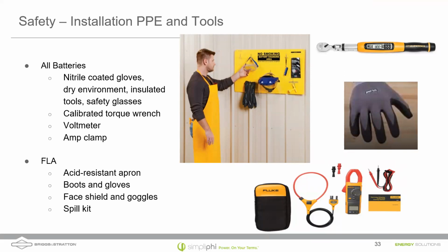I had some students working on putting together a solar-powered refrigerator with a battery bank. One of the students was using a wrench to tighten the lugs down on the battery. Unlike ours, our battery has breakers on it where you can switch the battery off, but this was a deep cycle lead acid battery without that kind of switch. He was using a crescent wrench and turned it, and it shorted between the positive and negative terminals. The student got very concerned because the wrench turned red hot and actually melted the lead terminals down through the battery casing itself.